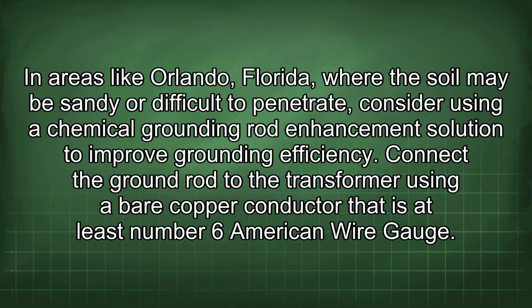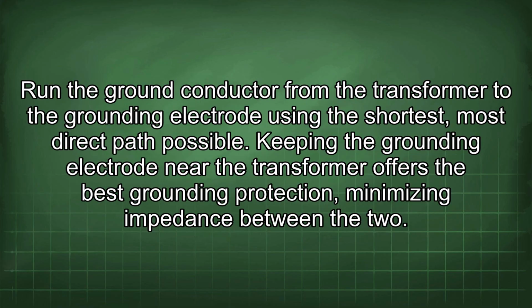In areas like Orlando, Florida, where the soil may be sandy or difficult to penetrate, consider using a chemical grounding rod enhancement solution to improve grounding efficiency. Connect the ground rod to the transformer using a bare copper conductor that is at least number 6 American wire gauge. Run the ground conductor from the transformer to the grounding electrode using the shortest, most direct path possible.